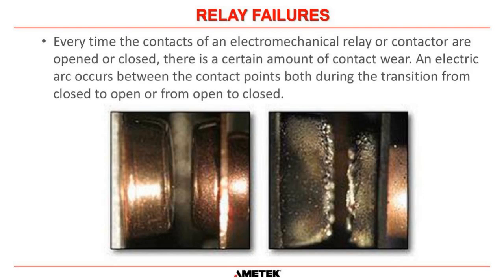You can see in the picture on the left that that's a perfectly brand new relay, and the contacts are clean, beautiful. That's what your contact should look like. And the picture on the right is what the exact same contacts look like after being in operation for a certain amount of time. Now, obviously, it depends how much they open and close, but every time any contact opens and closes, there is always going to be a small arc, because you're interrupting current or you are closing in on current. There is always going to be an arc, and it pits the surface.